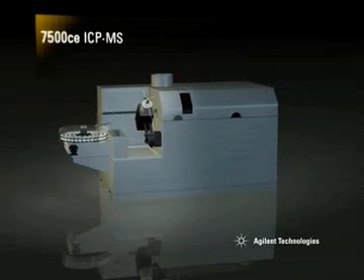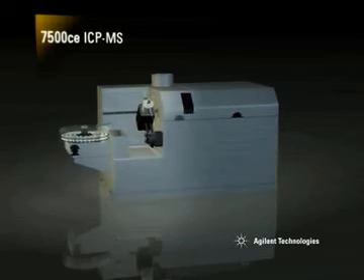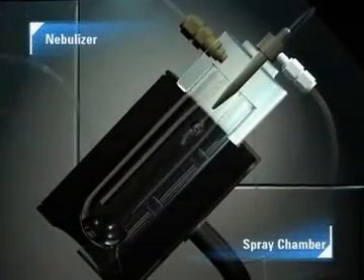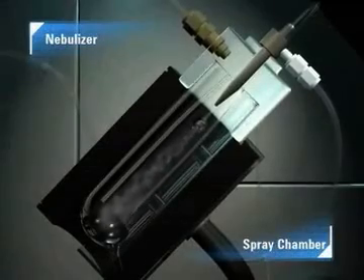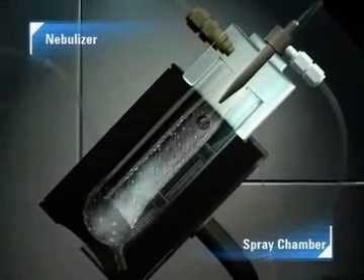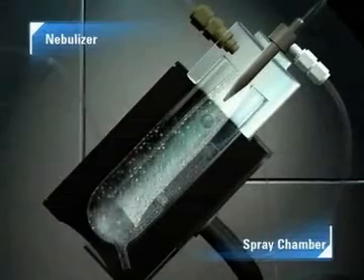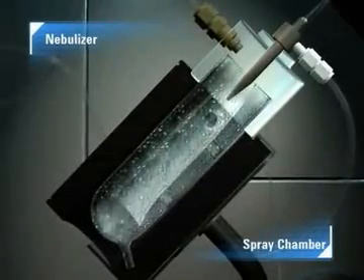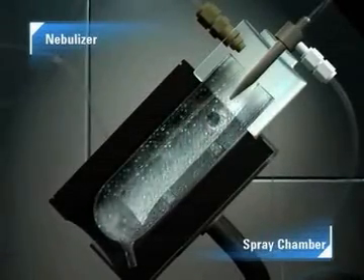Let's follow the journey a sample takes from its sample vial through the ICP-MS to the detector. Sample is pumped from the sample vial into the nebulizer, where it is mixed with argon gas to form an aerosol. Larger droplets are removed from the sample aerosol as it passes through the cooled spray chamber, and the fine aerosol is swept into the central channel of the plasma.